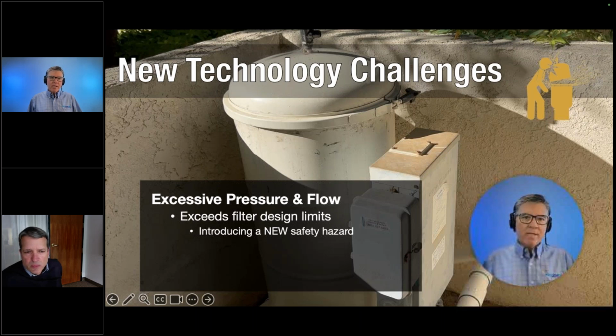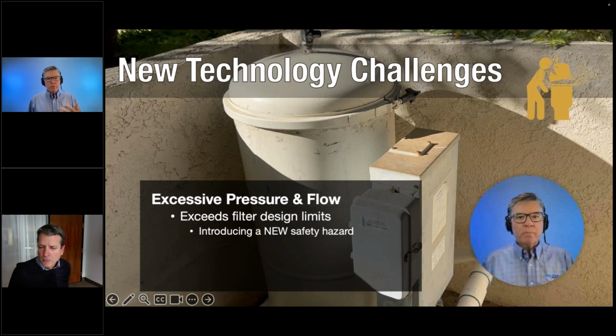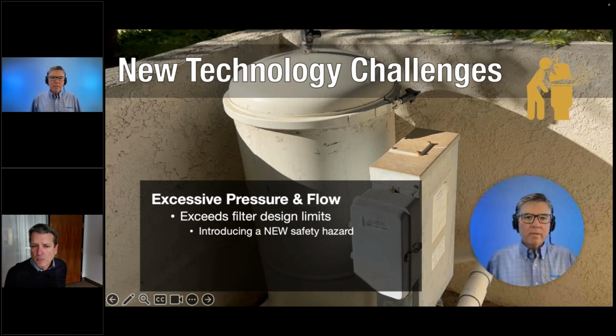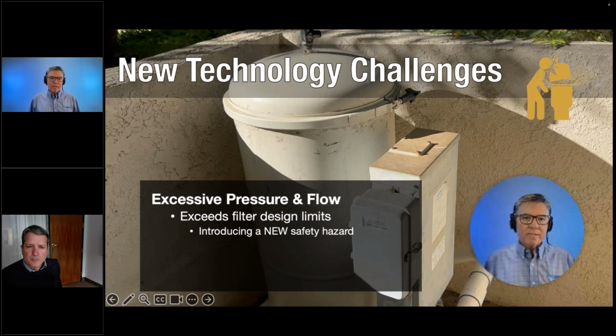Well, you can downsize below 1 horsepower and stick with a single speed, but even that's going to go away, I think, in 2 years, because the Department of Energy has now passed the dedicated purpose pool pump motor rule, and it will outlaw single speed pumps all the way down to 1/2 horse. That's going to have ramifications even on public pools: peristaltic pumps, chlorine booster pumps, venturi bypass again for acid draw and other things, and certainly our robotic cleaners and booster pumps. All of those are going to be going to variable speed because the motors are only going to be available in variable speed.